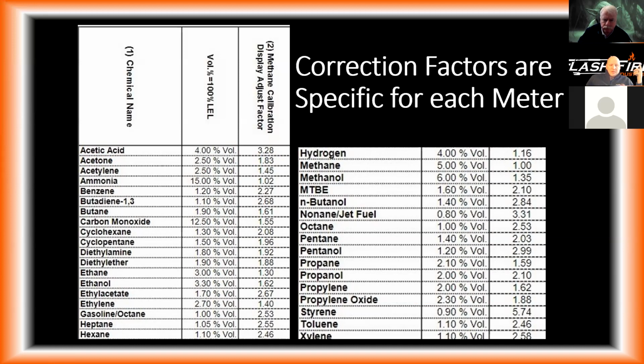Just do it in your head, multiply by 2 or 3. That'll get you within the ballpark if you don't know what you're metering. But the most important thing to remember is that this meter is only metering where you're holding it. Natural gas is lighter than air, propane is heavier than air. There's a very good chance that if you have 20% of the LEL on the first floor of a propane leak, then in the basement or in some void somewhere, you are at that explosive level.